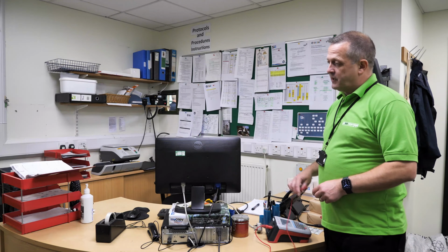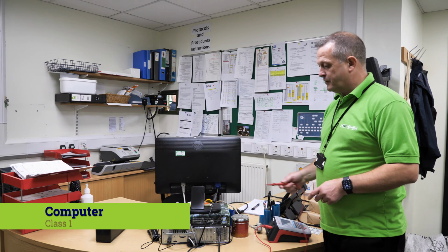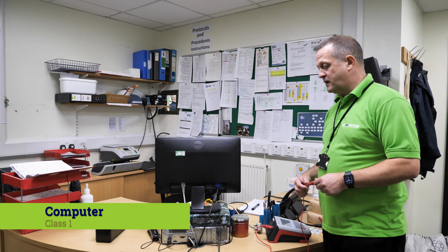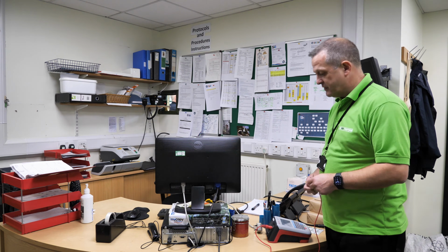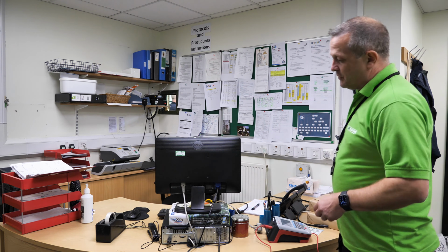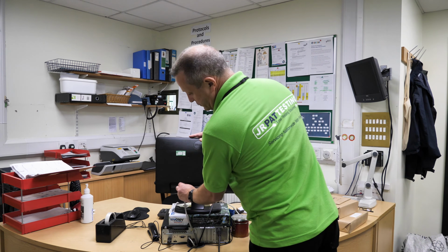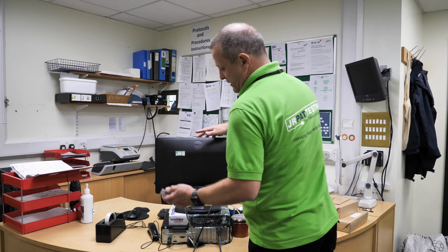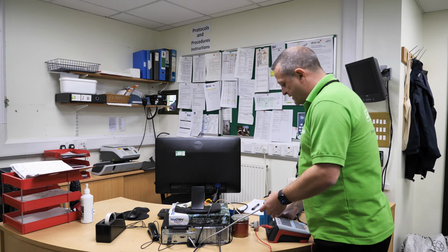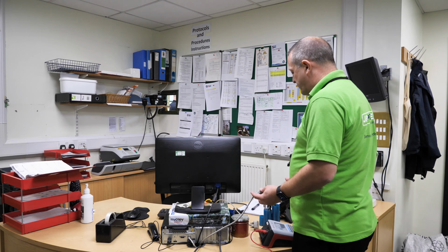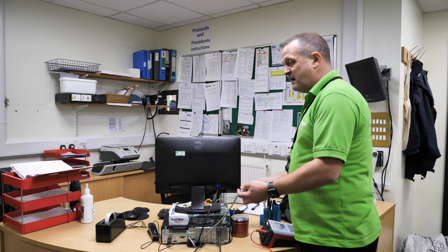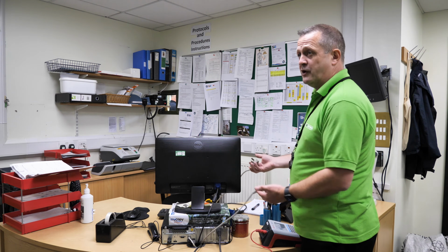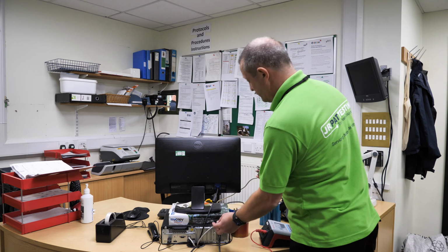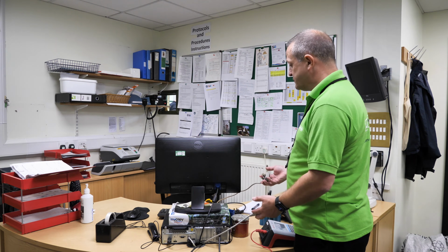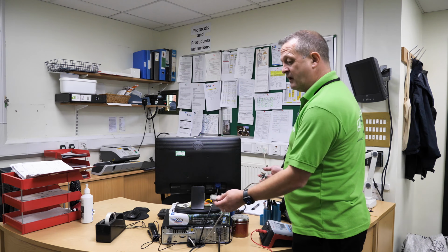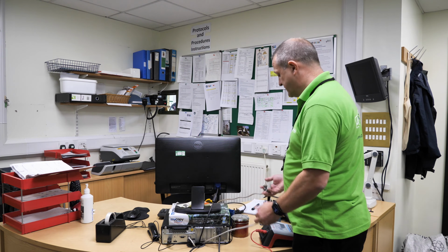So now we're going to be looking at testing a computer monitor and the computer base station. First of all, we're going to start off with the monitor, and we're going to be testing the IEC lead first of all. As the lead is actually classed as an appliance in its own right, we will test that separately, and the reason for that is that lead could effectively be used on any other similar type of appliance, i.e. it could be plugged into the computer for its power source, it could even be plugged into a kettle, hence the reason sometimes they're called kettle leads.